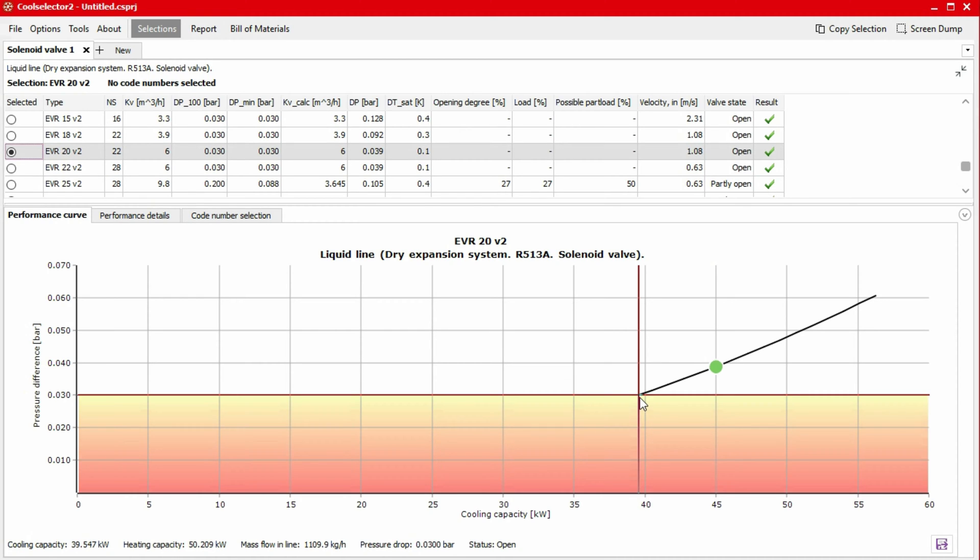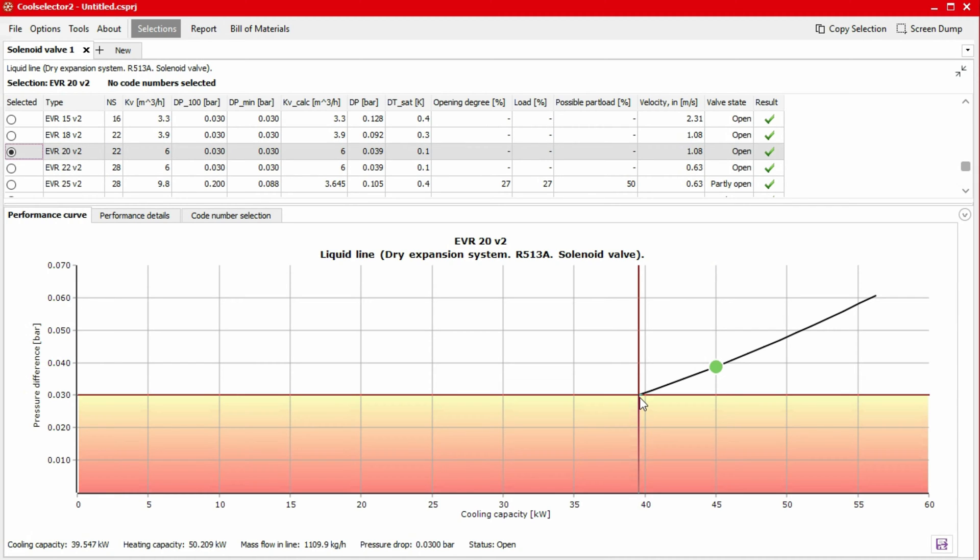This is because the selected solenoid valve is a diaphragm solenoid valve which requires a certain pressure drop across the valve to open. If our system will need to operate lower than this, then this valve will not be suitable, and we should select another.